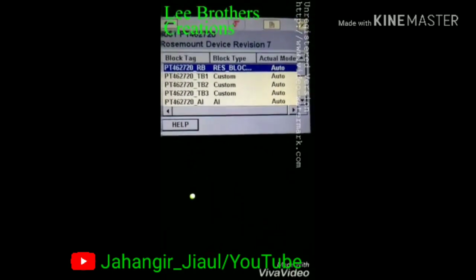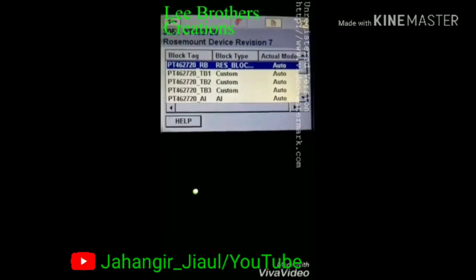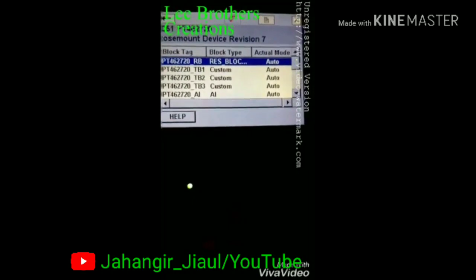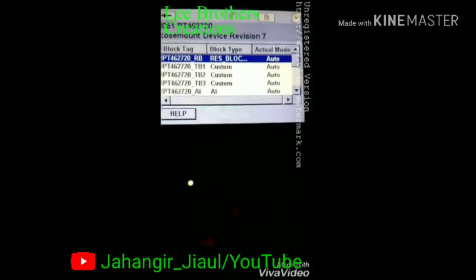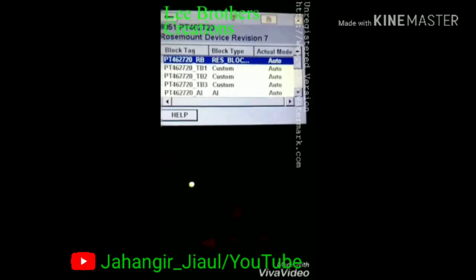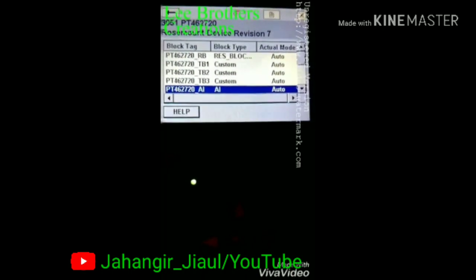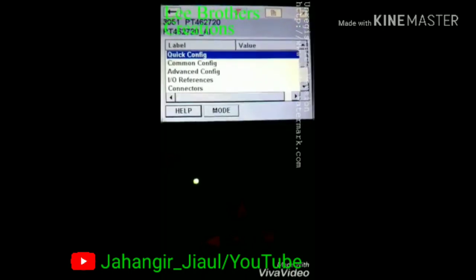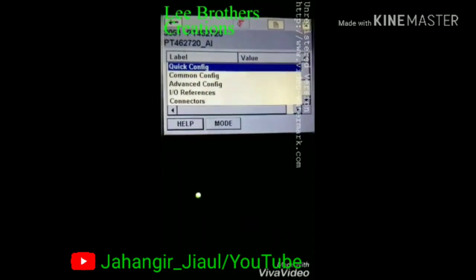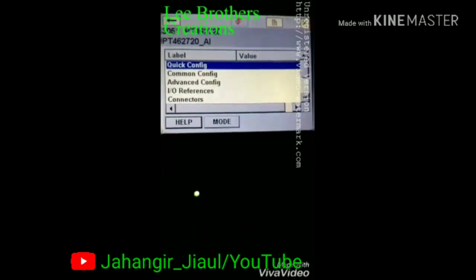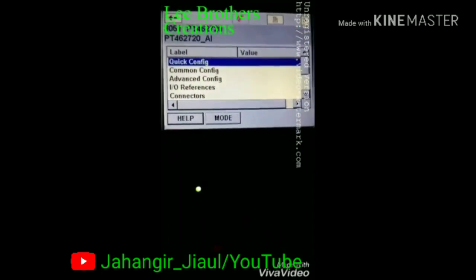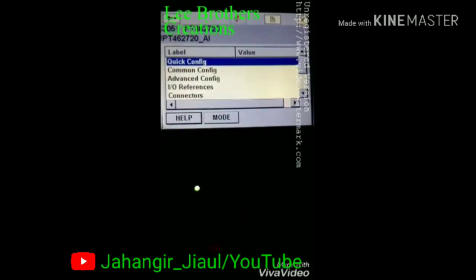When you enter that transmitter data list, it shows some blocks: there is a resource block, transducer block 1, transducer block 2, transducer block 3, and analog inputs. With our tag number on the analog input, we should enter this particular analog input to do the loop test. Once you enter that analog input, it shows quick config, common config, advanced config, and other things like I/O references and connectors.